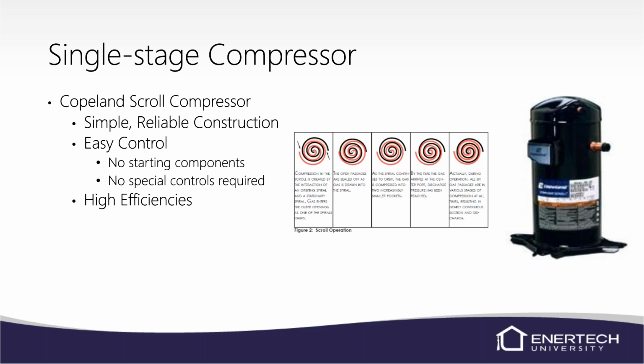Basically on any type of scroll compressor, there's no real starting devices. Now, you may have a soft start on there to lower amp draws on initial startup, but we don't have any starting capacitors or starting relays on these Copeland compressors. There is a run capacitor on it, and if the run capacitor is bad, the compressor is not going to operate. So that's the only part, besides a contactor, that it really needs to be operational for the compressor to operate. There's no special controls for the compressor, and basically they're a high efficiency compressor.